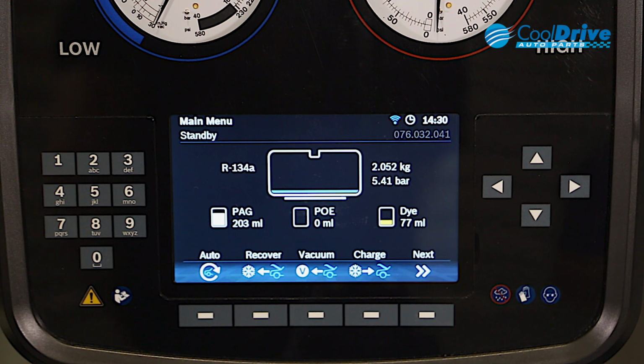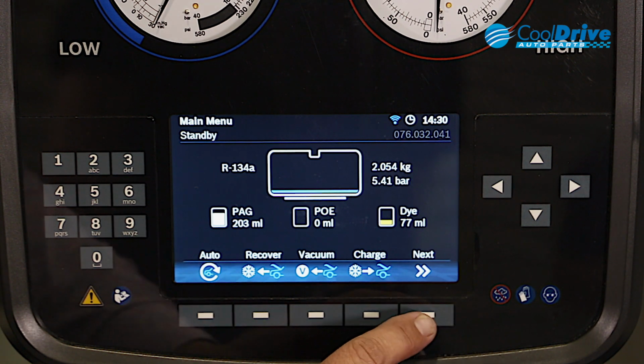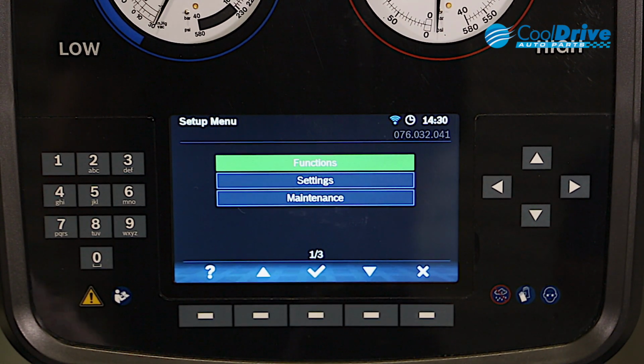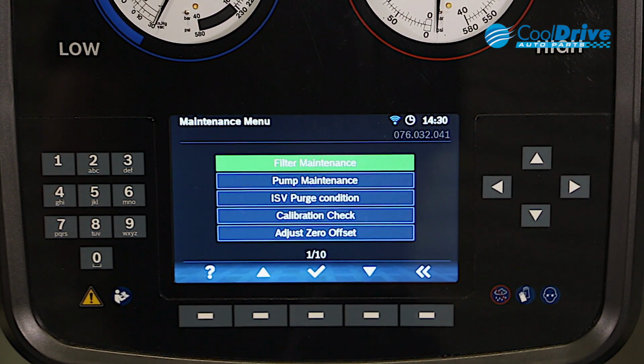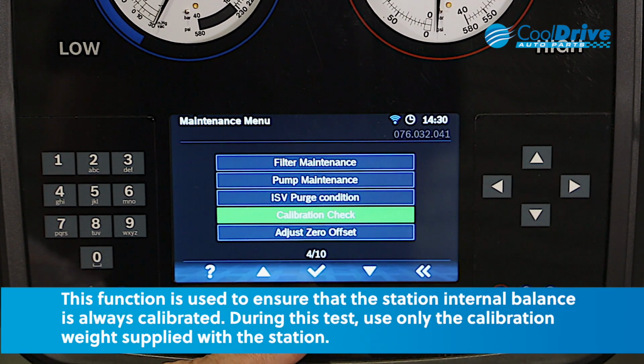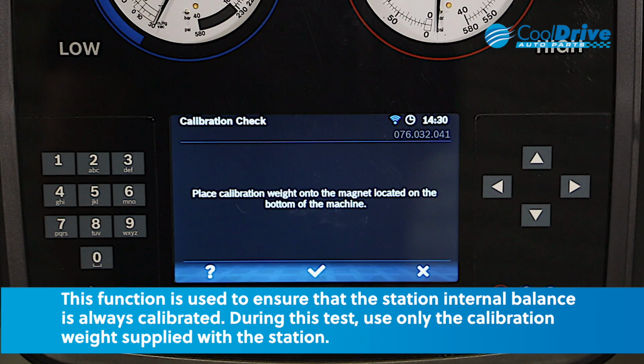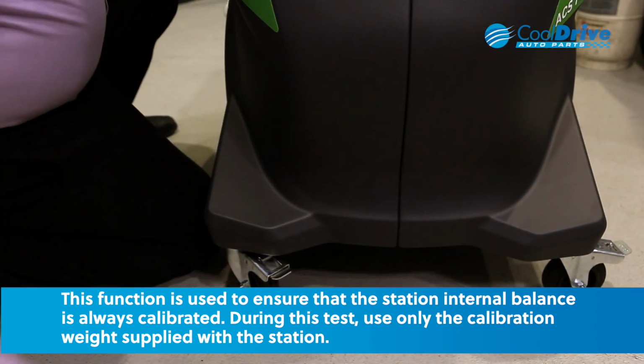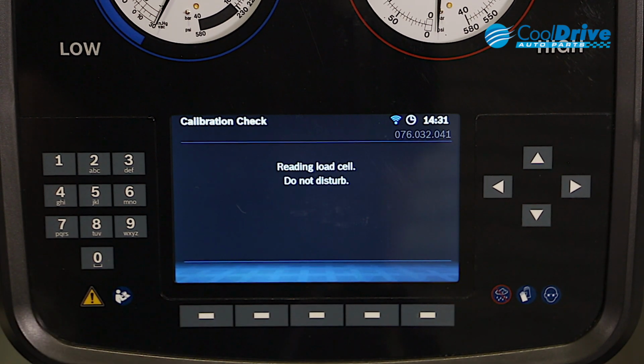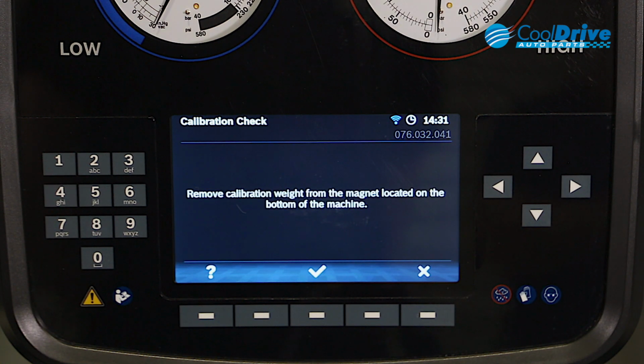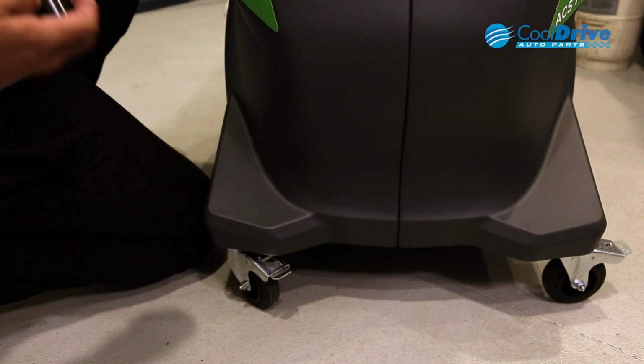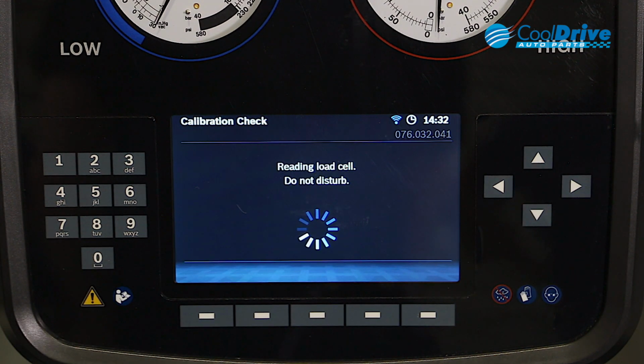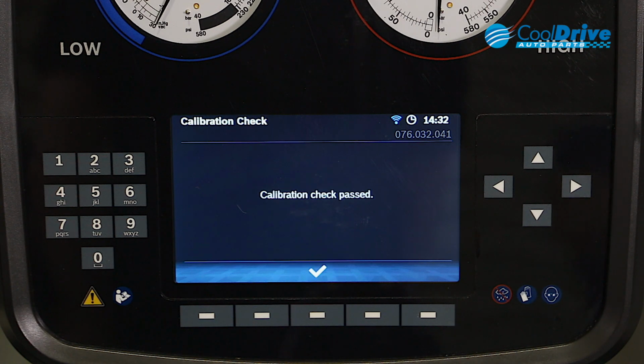To check the accuracy of the equipment, we can perform a calibration check. To do this, we have to access the main menu. From the main menu, we go into maintenance. From maintenance, we scroll down to calibration check. The machine will then prompt us to place the calibration weight onto the magnet from underneath the machine. Once the weight's been placed on the bottom of the machine, it's as simple as pressing enter. Without disturbing the machine, it will then prompt us to remove the weight from the bottom of the machine. Once prompted to remove the calibration weight, we press enter and the process passes.